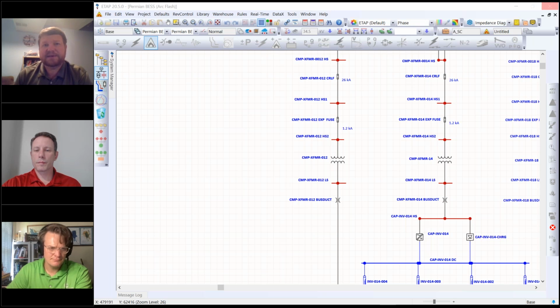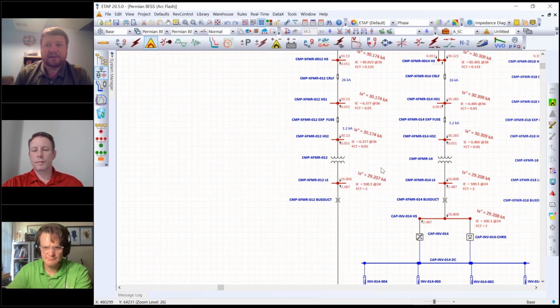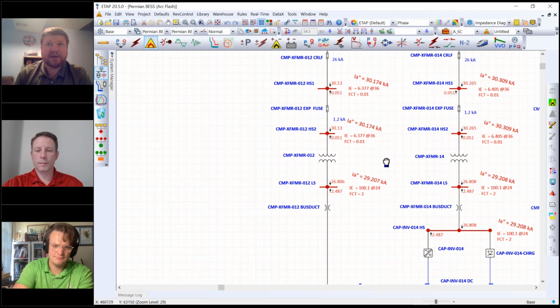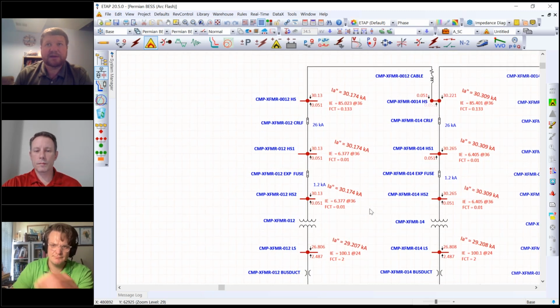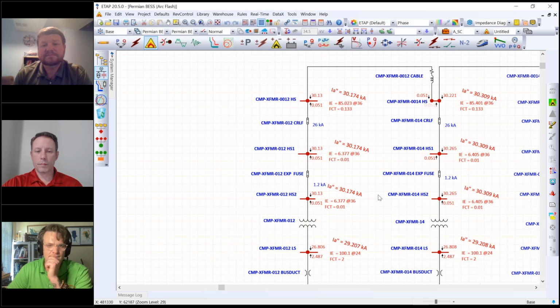This is a kind of a known AC arc flash problem. It's seen across the entire industry and a lot in industrial applications where they have relatively high voltage connections to very large station transformers. Yeah, so ETAP is showing 100 cals at the low side because the fuse just doesn't pick up at all for a low side fault. Yep, and that's modeling the CLF fuse that is in place here. So current limiting fuses don't really work unless the current actually exceeds the value of the fuse in the first place.